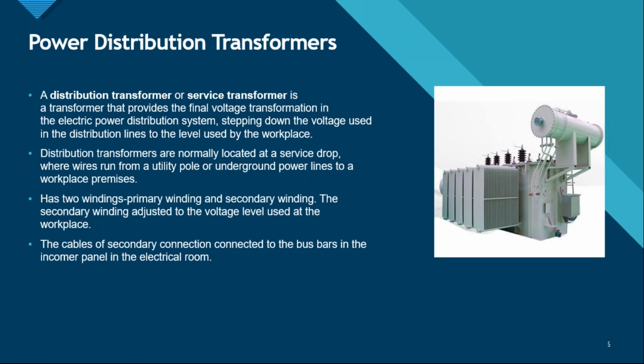So the power distribution transformers, right? You must have all seen these kind of transformers that might be there in your substations. A distribution transformer or service transformer is a transformer that provides the final voltage transformation in the electrical power distribution system. Right? There can be two types of transformers, a step-up transformer or a step-down transformer. Step-up transformer basically increases the voltage, and step-down transformer reduces the voltage, right? Mainly in all industries, we have a step-down transformer that reduces the voltage from 11 kV to maybe 440 volts or 450 volts. All right, so that voltage rating can be used for industrial supplies. Stepping down the voltage used in the distribution lines to the level used by the workplace.